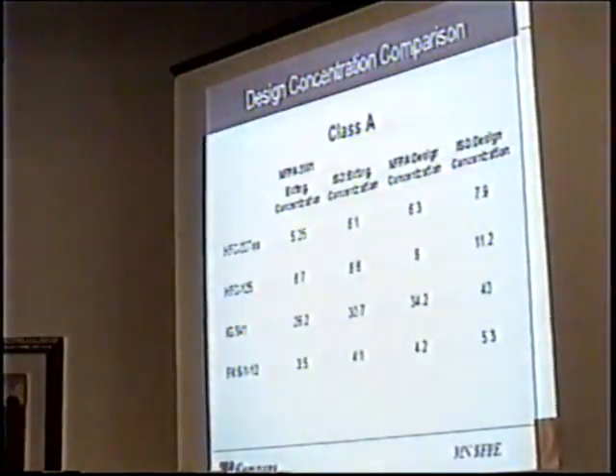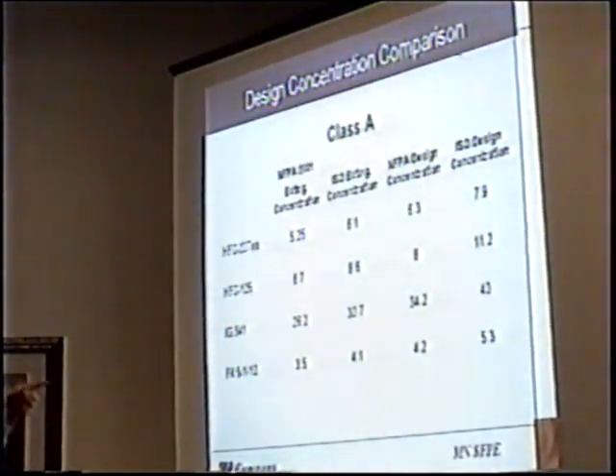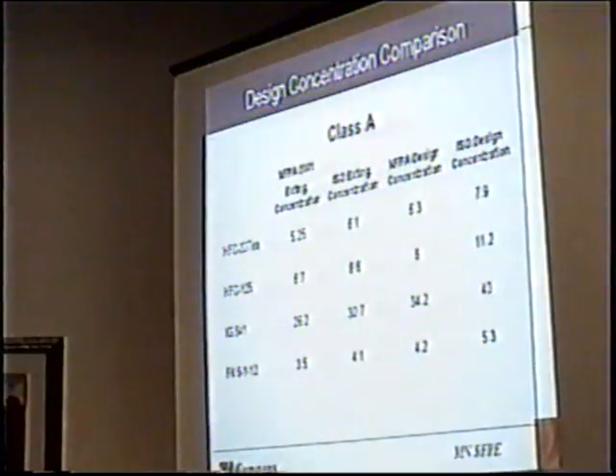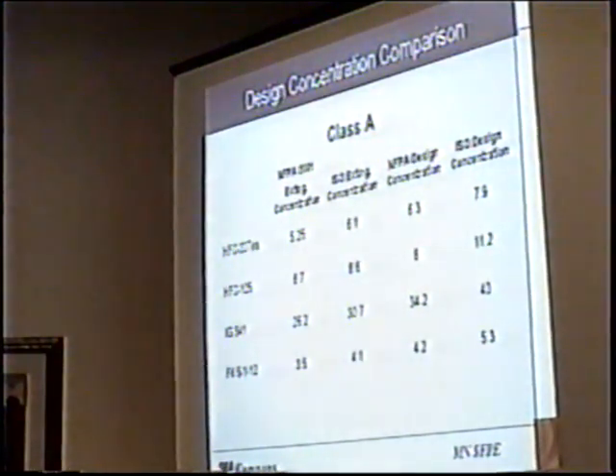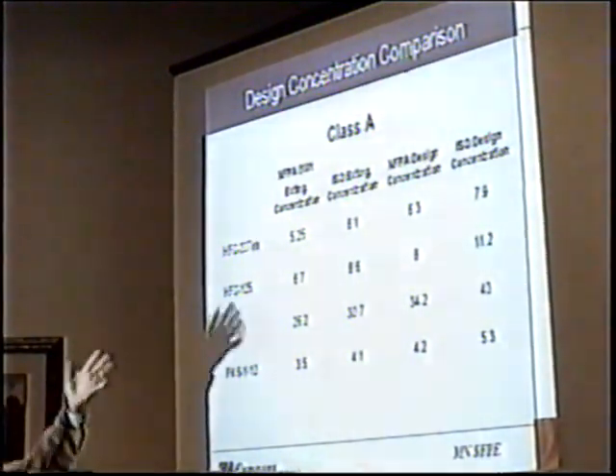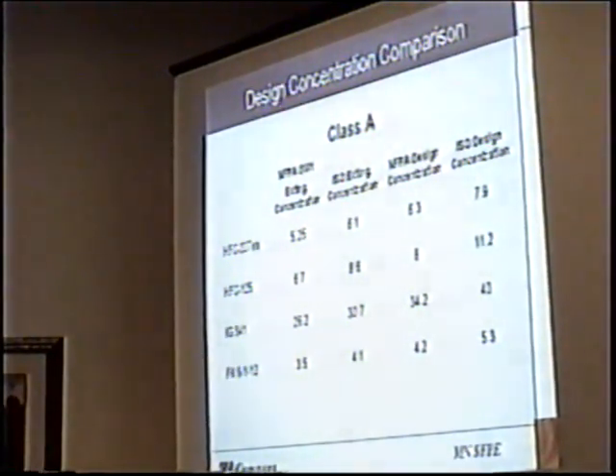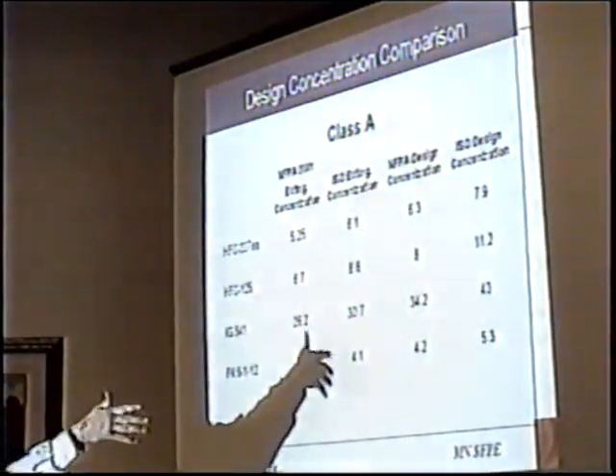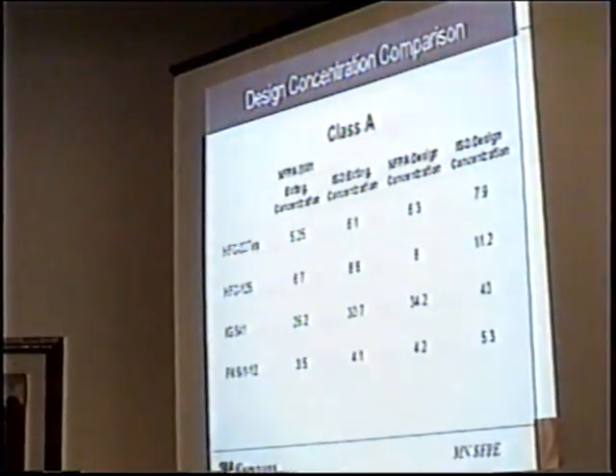You look at the NFPA design concentration is lower than the ISO design concentration, and that's because the two standards were supposed to have test protocols that were the same, but harmonized, if you will. But even with the same people on the committees, you can't get it, and you start getting politics involved with different countries and cultures mixing together. We couldn't get 2 protocols that were the same. So now the ISO standard has design concentrations that are significantly higher than what you have for NFPA design.